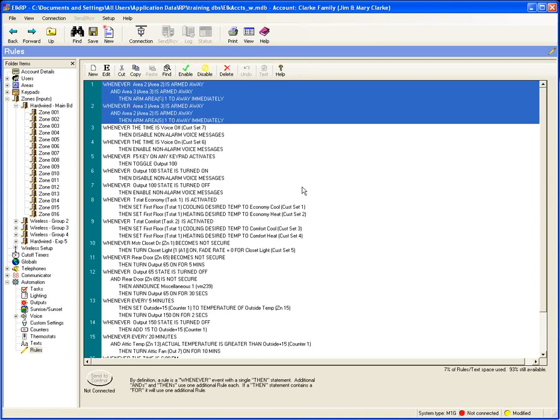My examples one and two are related to common area. If I want to automatically arm Area 1 when Areas 2 and 3 are armed, I have to set up two rules. In rule one: whenever Area 2 is armed away and Area 3 is armed away, then arm Area 1 to away. I need a second rule because the 'whenever' is the trigger and the 'and' is a condition that must be met at the time the trigger occurs. You can't know which order Area 2 and Area 3 are going to get armed, so you have to account for both scenarios.